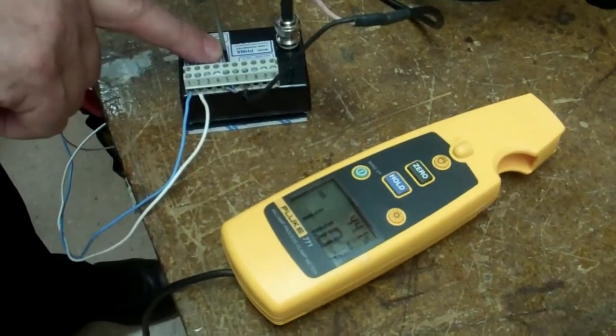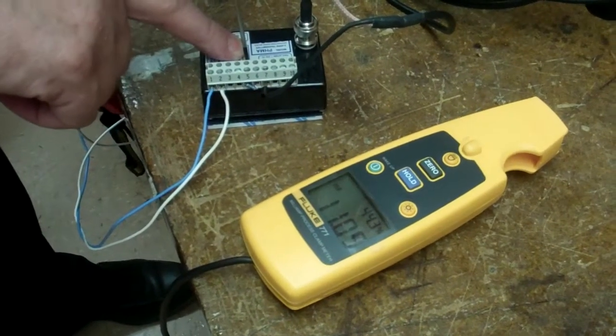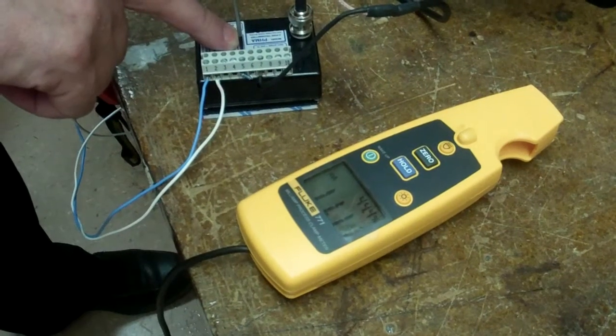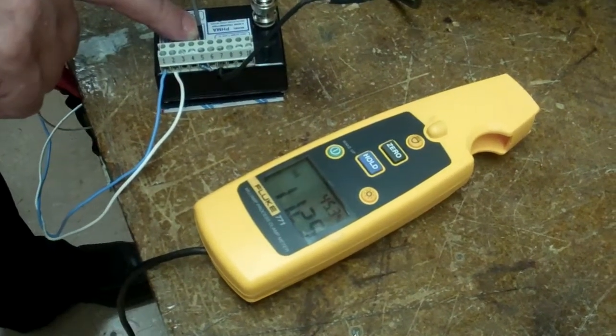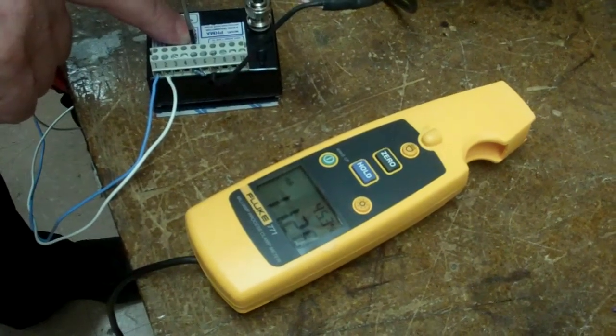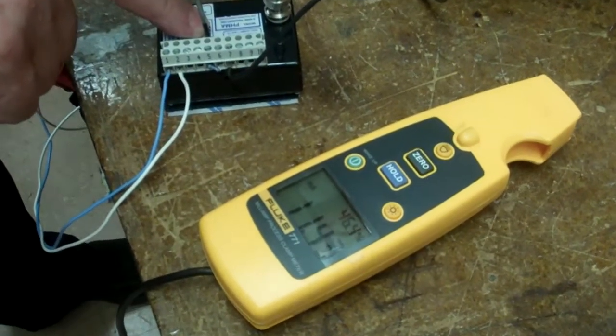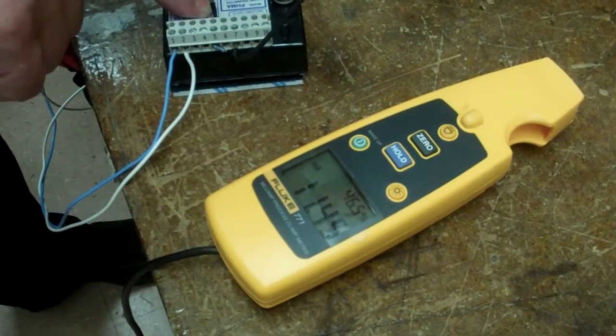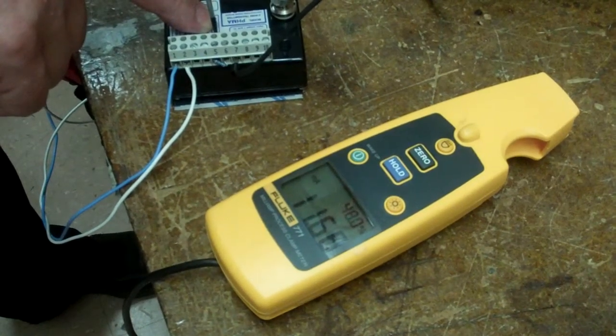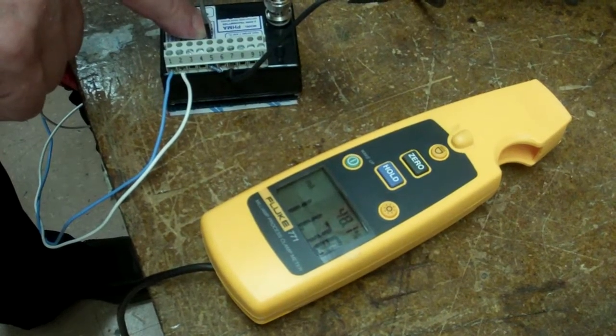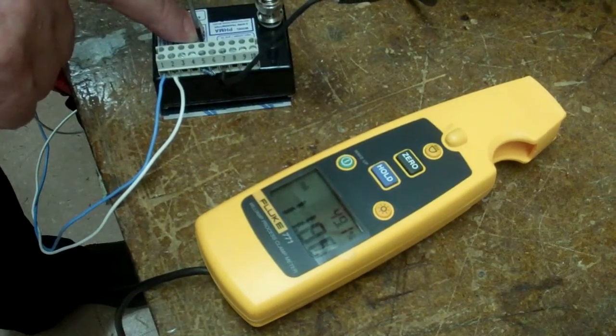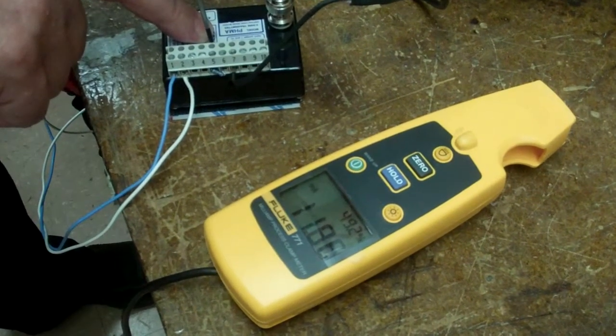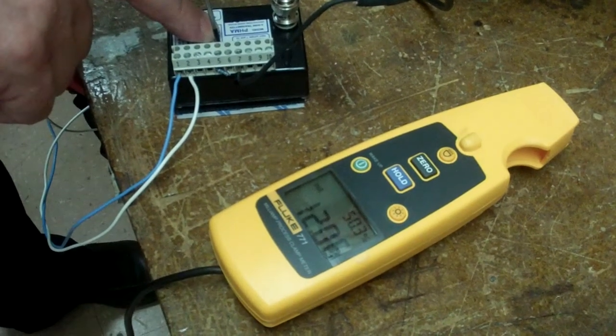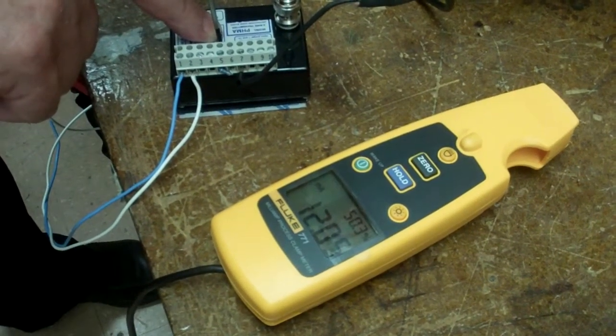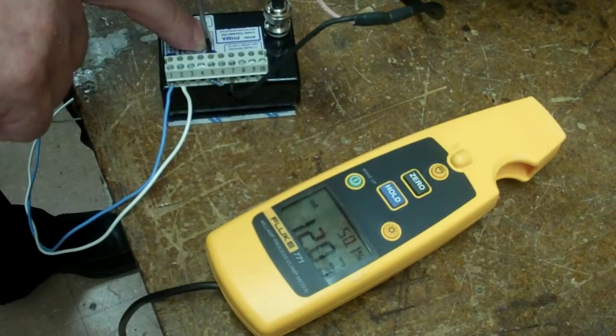This is a logarithmic analog circuit in here. There's a time delay. That means there's capacitors and inductors at play in here. So it is a slow response circuit, unlike a light switch which turns lights on and off. So you can overshoot, you can undershoot. So I'm getting close to 12. And then I'm going to go to the pH of 10, which should go to 15.4. And I'm going to come back to the 12, and you go back and forth a couple times until it reads 12 and 15.4. There, I just broke over 12. Back it off a little bit. Close enough for the first pass.